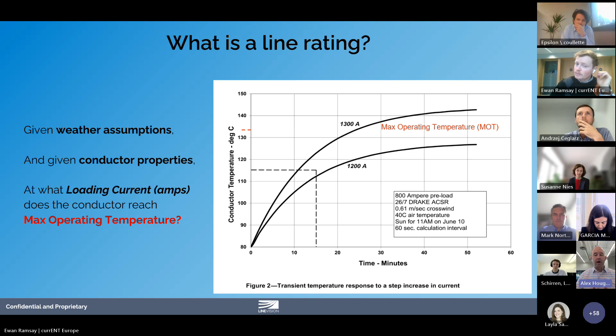Well, again, these are thermally limited assets. These are pieces of metal hanging out there between towers. And really, there are two things that will determine what that maximum temperature is. The first has to do with safety. So the hotter a piece of metal gets, the more those molecules expand and sag. And if they sag too much, you can violate a clearance limit where the line will sag to a point where it can interfere with vegetation. It can interfere with the crossing of motorways or rivers. You can't have that piece of metal sagging too far from a safety standpoint.